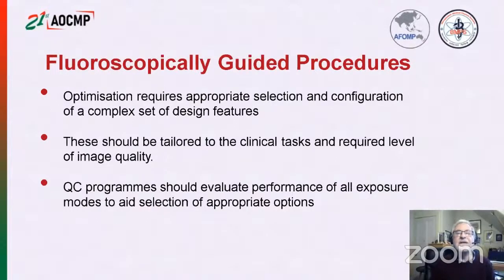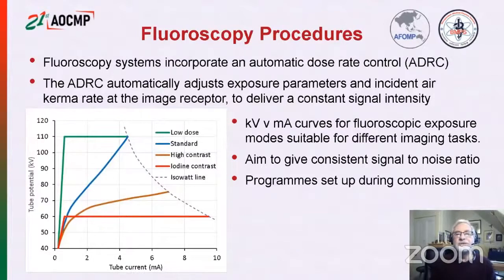For fluoroscopy guided procedures, optimization requires appropriate selection and configuration of a complex set of design features. So these need to be tailored to the clinical tasks and the required image quality level. And QC programs should evaluate the performance of all the exposure modes to aid selection of appropriate options. Fluoroscopy systems incorporate an automatic dose rate control, and this adjusts the exposure parameters and incident air kerma at the image receptor to deliver a constant signal intensity. But the kV and the mA can be adjusted in different ways, and this graph shows how the tube potential and tube current might be adjusted with respect to each other.